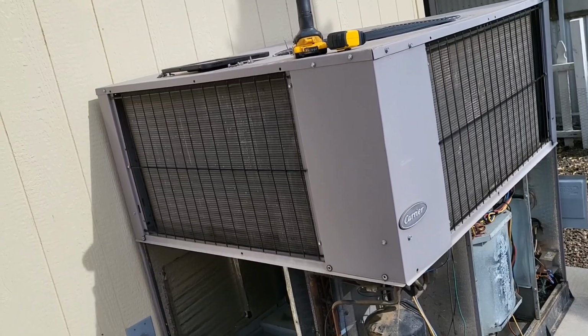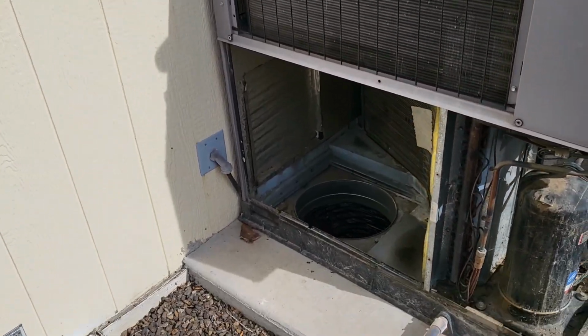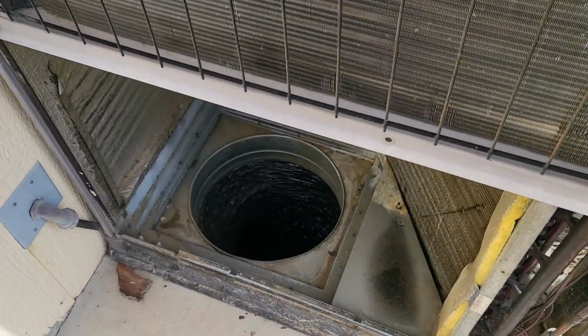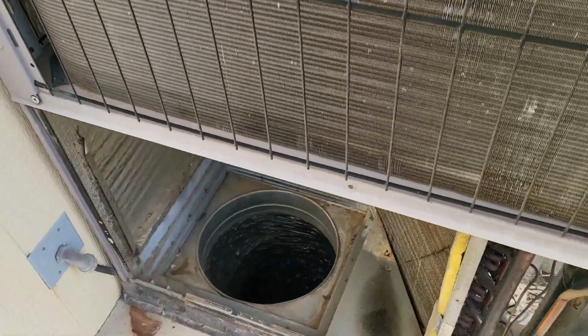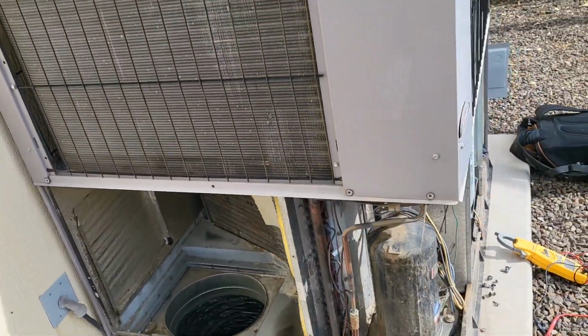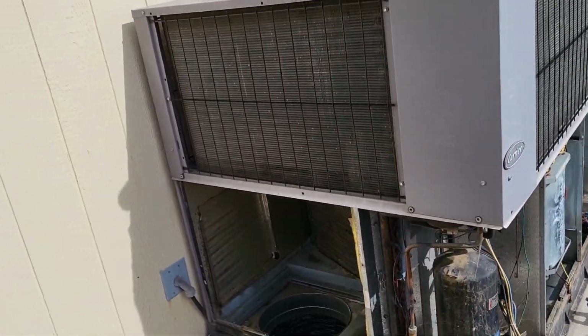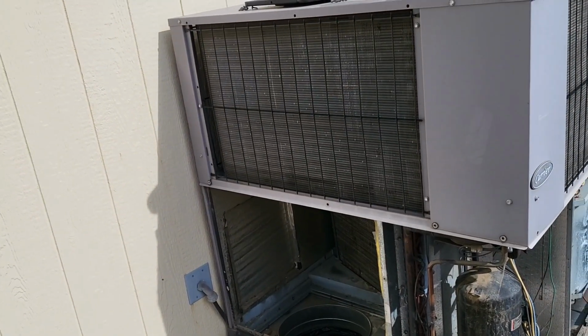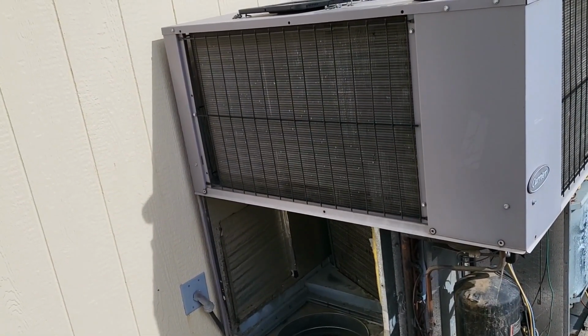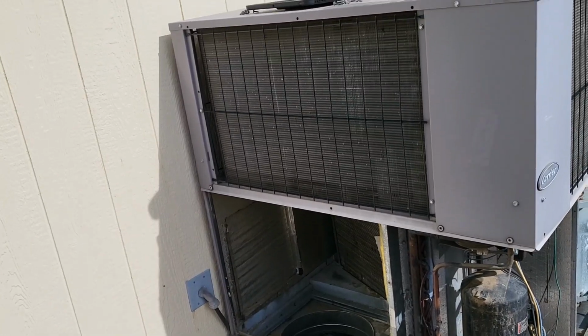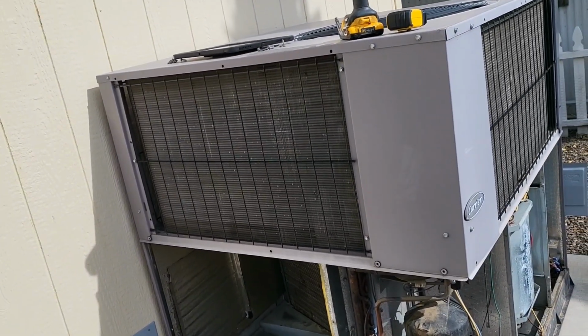It's not condensing. The ductwork, the return is only 14, and this is a 4-ton unit. So ideally it should be at a very minimum 16 if it was a short run, but this is not a short run, this is a very long run. Should be 18 or 20.